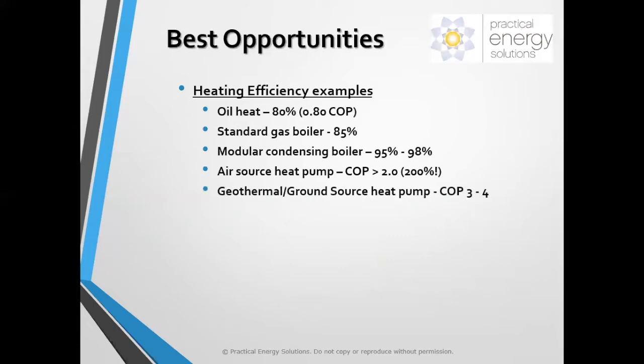As you get to a ground source heat pump, or geothermal, as we call it, the coefficient of performance can be 3 to 4, and actually newer systems can be over 4. So you're looking at really 400% efficiency. For every BTU you put in, you're getting 4 BTUs out. Whereas for the oil heat, every BTU you put in, you're only getting 0.8 BTUs out. So much improved as you get to these other systems.